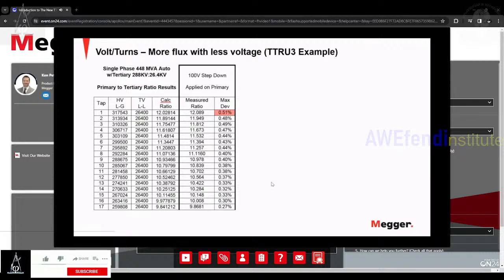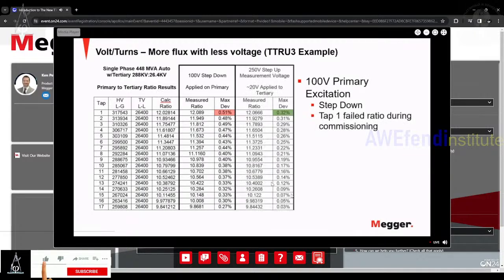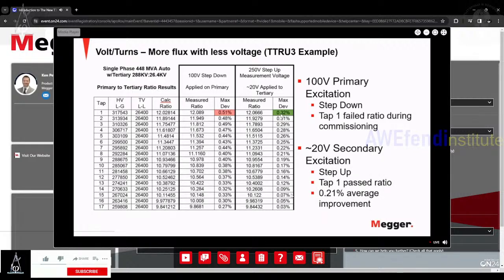For example, this is actually taken from the TTRU3, which was launched in 2019, just to give an example of how this step-up testing method works. By applying 100 volts step down, you would see a max deviation on one of the higher taps. Again, this is on a very big transformer, of 0.51%. But if you are able to generate more voltage on the primary, like we are able to with the TTRU1 and the TTRU3, then you can see a dramatic improvement of that max deviation for that tap. And overall, the whole transformer that was measured was about 0.2%, which is a big improvement over that 100-volt step-down method.